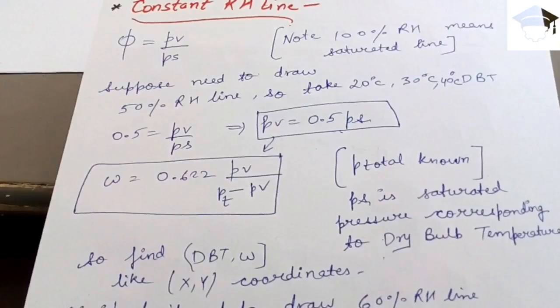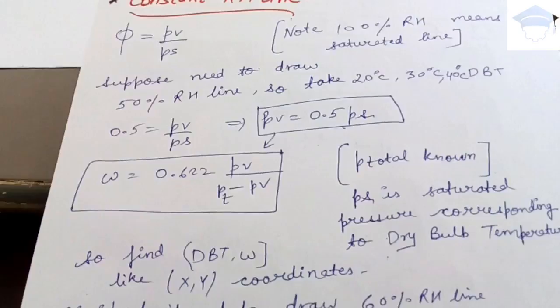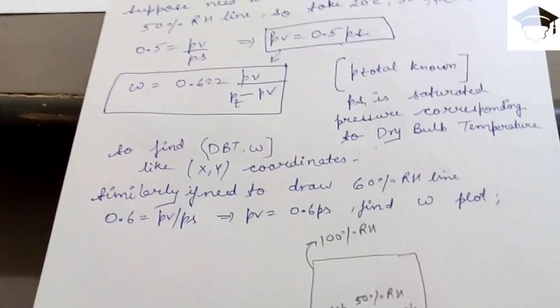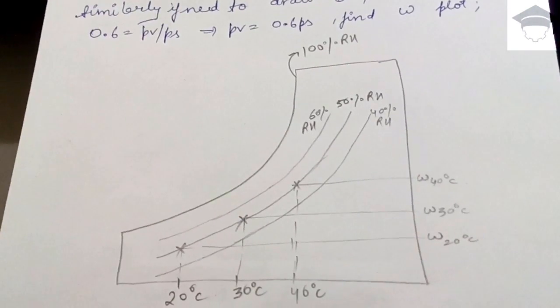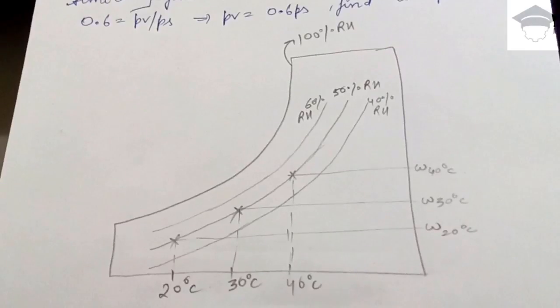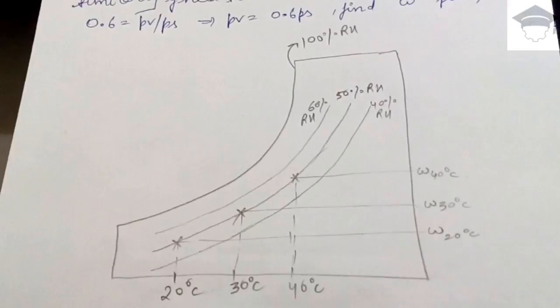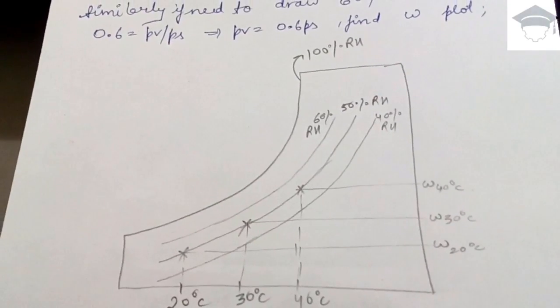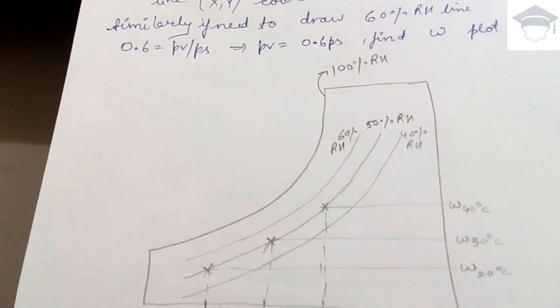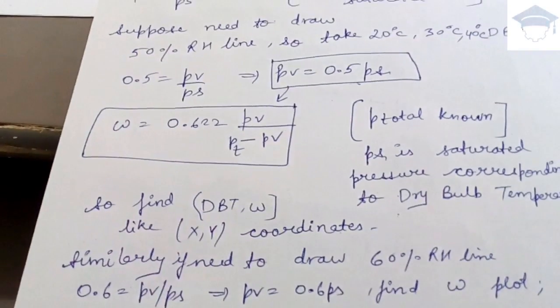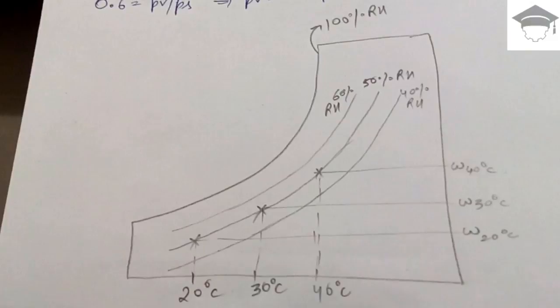Repeat for 30°C: find saturation pressure at 30°C, find omega, then move up from 30°C and left from omega at 30°C — that gives the second point. Similarly for 40°C: move up from 40°C and left from omega at 40°C for the third point. With three points, draw a smooth curve — this represents the 50% RH line.